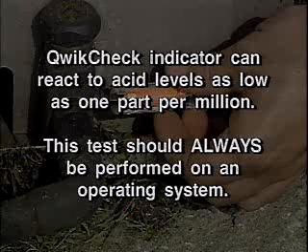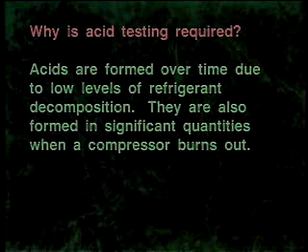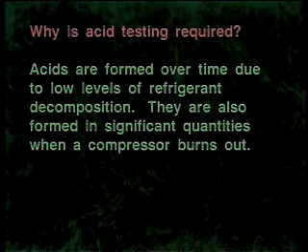Some common questions come up regarding the need for acid tests and using QwikCheck to test for acid. Why is acid testing required? Inorganic acids, such as hydrogen chloride and hydrogen fluoride, are formed as a result of refrigerant decomposition. This decomposition can take place gradually over time and is accelerated by the presence of moisture in the system. These acids are formed in significant quantities during a compressor burnout.